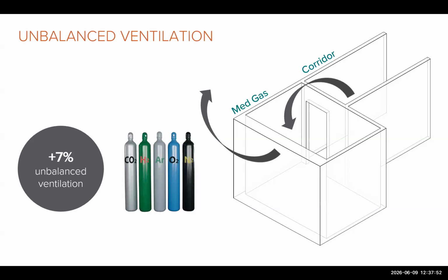Another challenge we faced near the end of design was med gas exhaust. Per Phius, building ventilation, or the intake air and exhaust air, must be balanced to within 10% of each other. So the challenge with medical gas storage rooms is that they are exhausted continuously, and that exhaust is not allowed to pass through the ERV system. So 1,000 CFM of air is being constantly exhausted from our medical gas room.